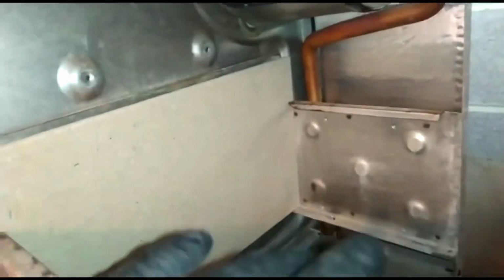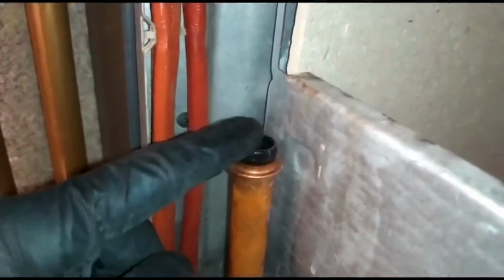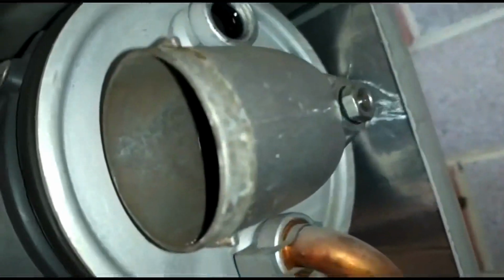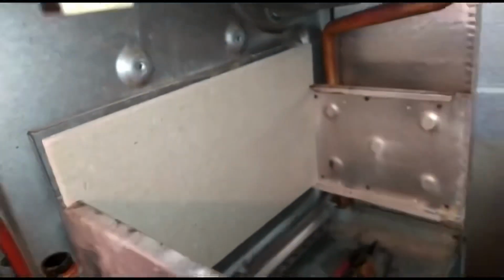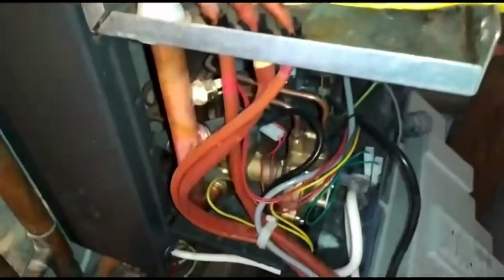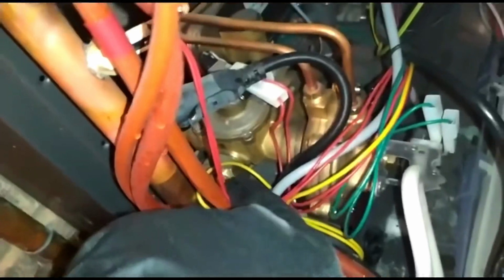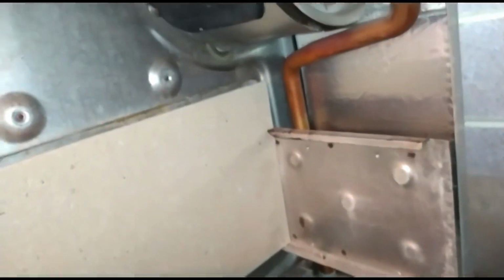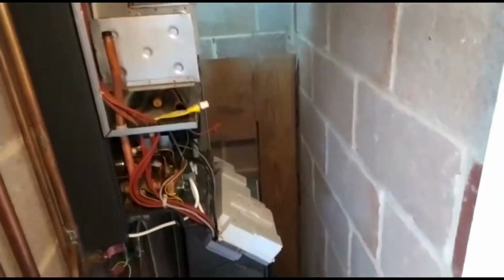And there we go. So who else strips off the main heat exchanger when replacing the rear insulation board on these? I have managed to wiggle them out before, but then I always end up getting these joints leaking. So who else takes the main board off? It's a little bit more involved - you've got to replace all the little O-rings and end up replacing the one down on the hydraulic block here. But yeah, who else has fun doing that when there's no room to work?